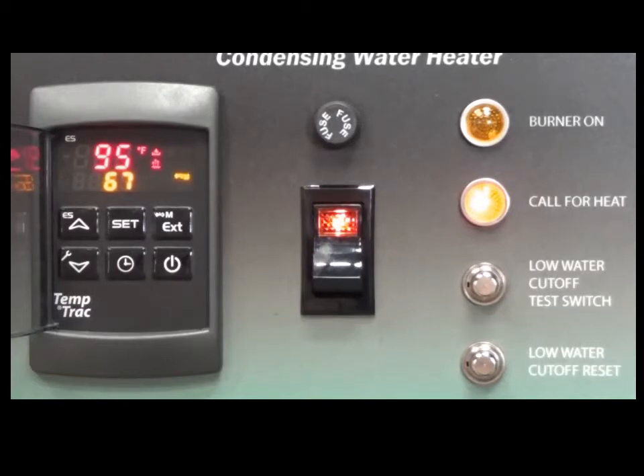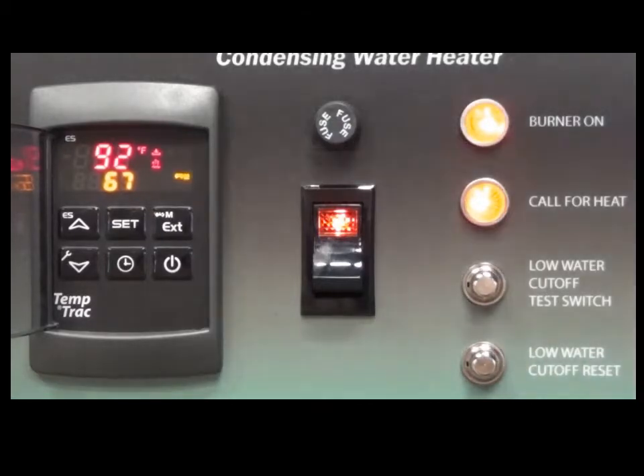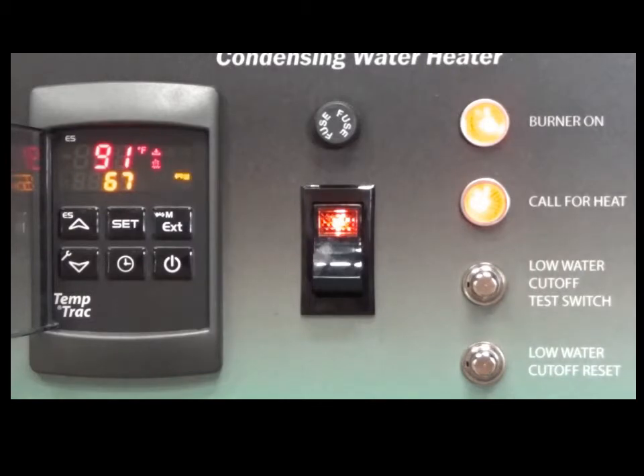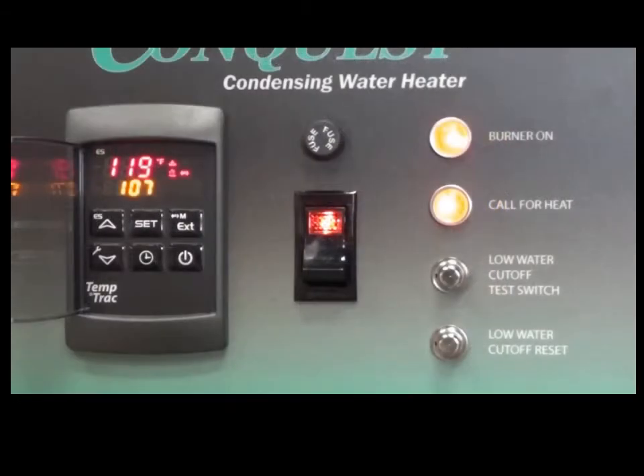When the gas valve is energized, the burner on light illuminates. After a 10-second delay, digital input 1 is deactivated and the flashing valve M icon shuts off and is replaced by a steady valve icon. When the call for heat is satisfied, the burner on and the call for heat lights shut off. Digital input 1 is then reactivated and the valve M icon will illuminate and flash.